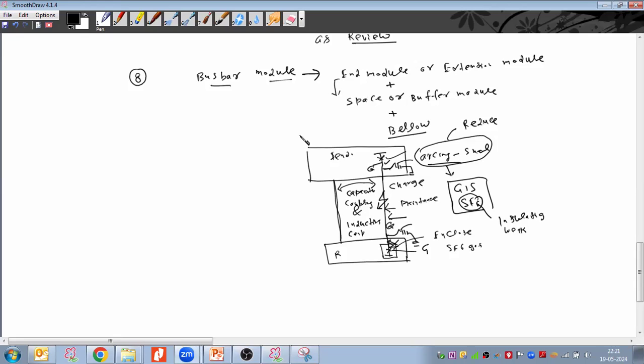So due to this reason, in GIS, in every line bay, we have to take the high-speed earthing switch. Otherwise, operations with a motor have some inertia. The motor takes time to get up to speed, so we do not take a motor. We have to take the spring, which has no inertia and operates faster compared to a motor. So every line bay must have a fast acting earthing switch which is operated by the spring. Am I clear why we take the high-speed earthing switch on the GIS?